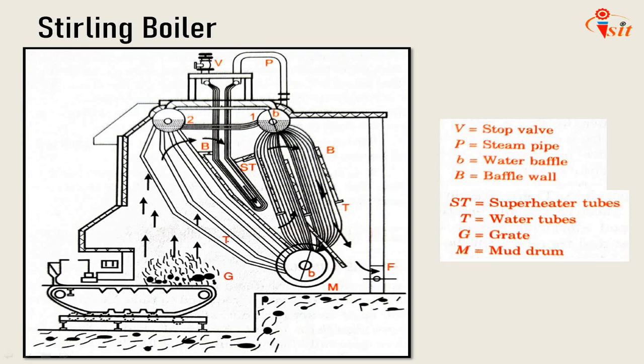The next boiler is the Stirling boiler. The Stirling water tube boiler is an example of a bent tube boiler, which is the second category in the classification. The main elements of a bent type water tube boiler are essentially drums and headers connected by bent tubes. For large central power stations these boilers are very popular, having steaming capacity as high as 50,000 kg per hour and a pressure as high as 60 bar.